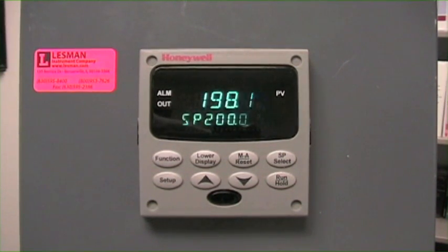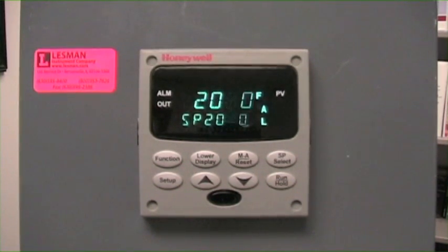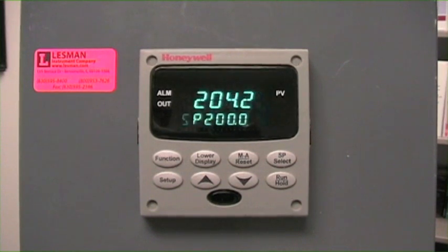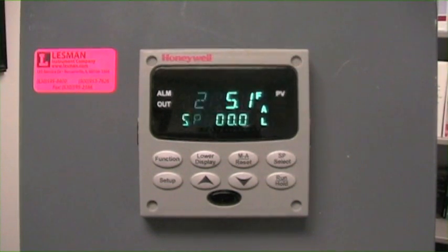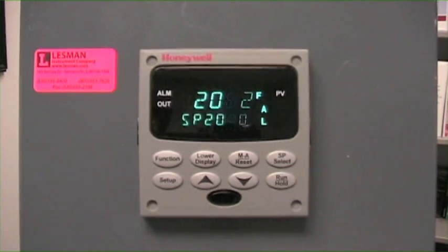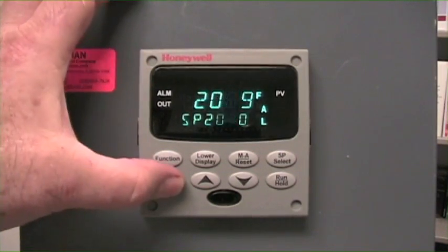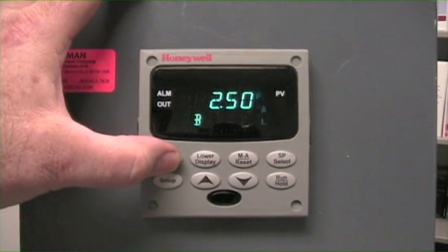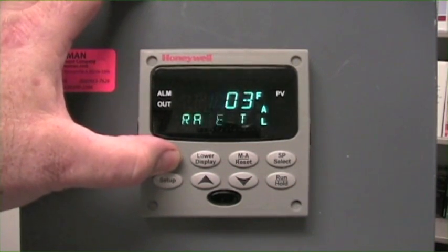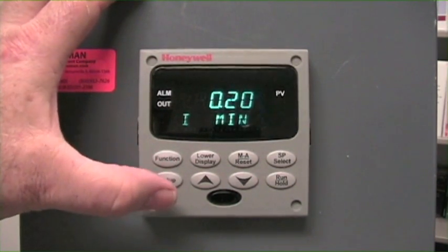The good news is that Honeywell's auto-tuning algorithm called Accutune can tune probably about 2/3 of the loops out there. Accutune excels at tuning temperature control or thermal loops. The purpose of tuning is to match the controller's response to the actual process operational conditions. What Accutune does is it alters the controller's output, watches the response, and then calculates the three tuning constants, which are proportional band or gain, rate, and the integral or the reset function.